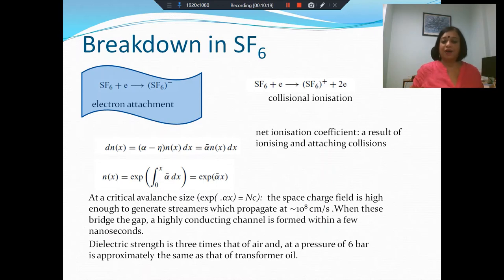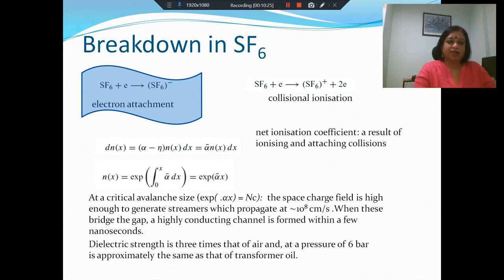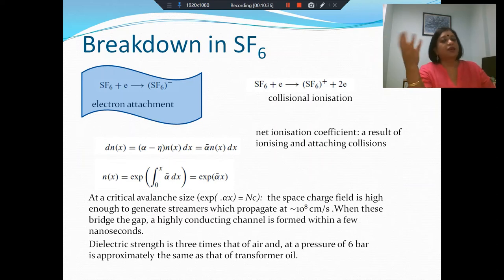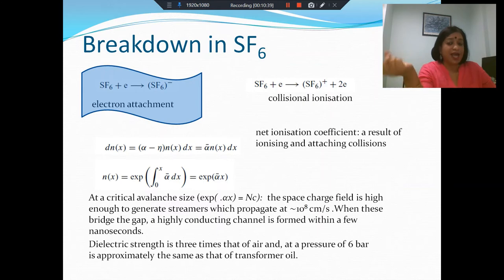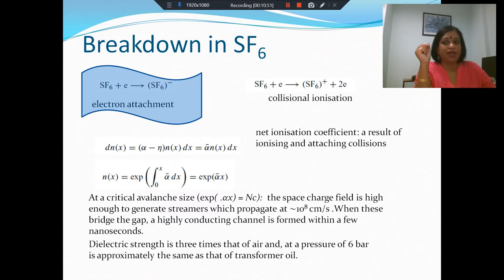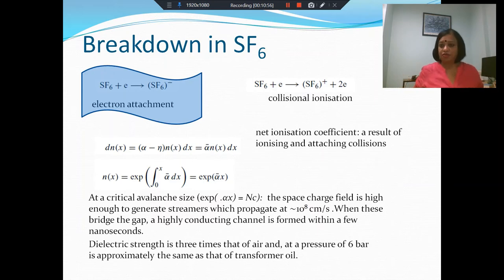Whenever we have breakdown, it progresses by electron multiplication — ionization. Whenever there is a collision between a neutral particle and an electron, the electron may impart energy and produce more than one electron. But in SF6, when a neutral molecule collides with an electron, instead of producing more electrons, it captures the electron. So instead of multiplying, it removes electrons from the picture, and as a result it retards breakdown.